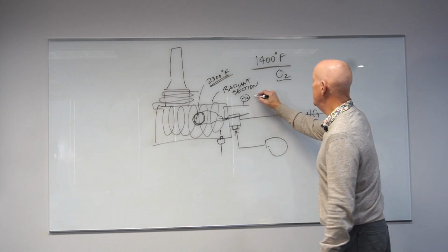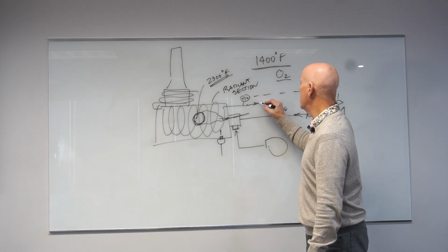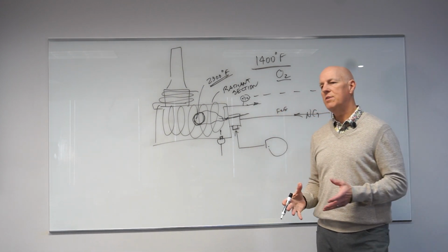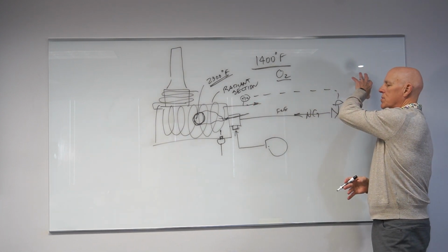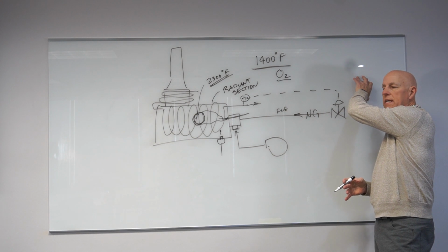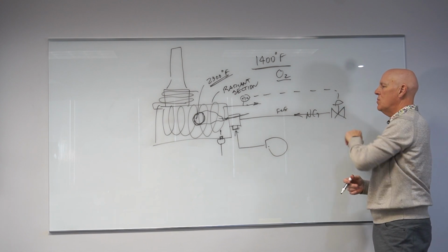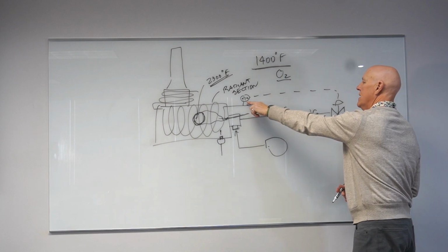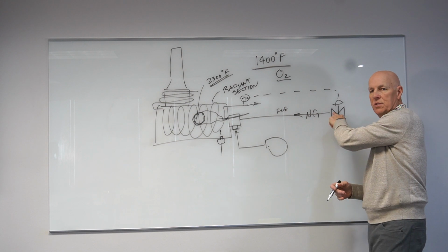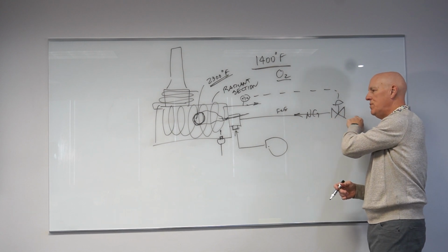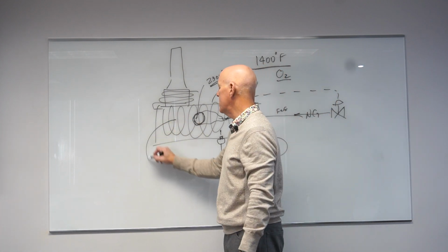So let's say you have a situation where this process fluid is going somewhere to users, and it doesn't need much heat for whatever reason, we have more heat than we want. So what happens? That says, this is hotter than we want. Pinch this back, lower the fuel going in here. Guess what happens when that happens? Well, this gets cold in here.